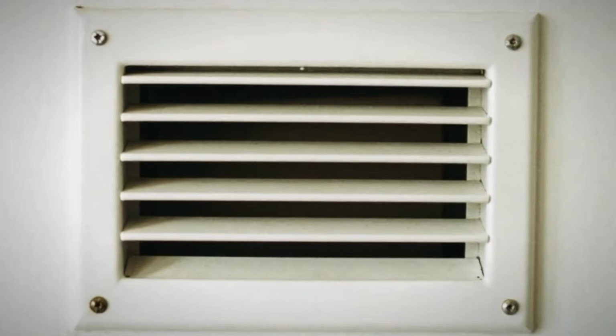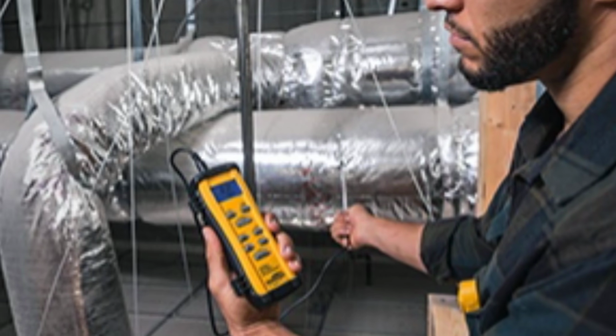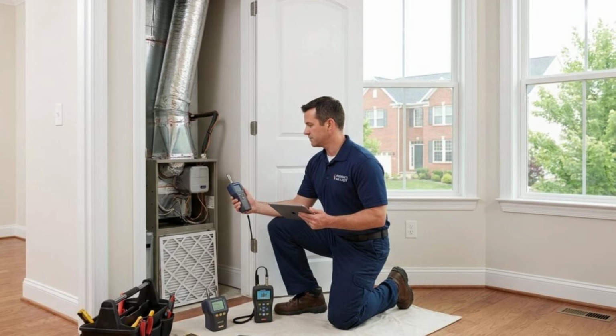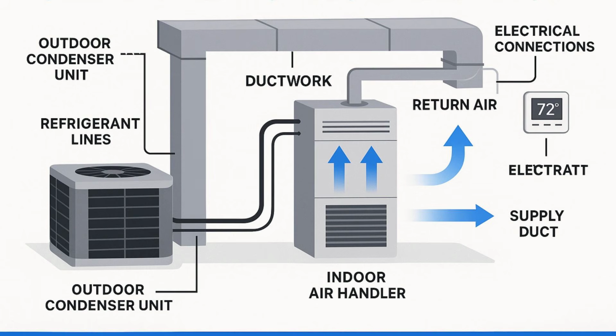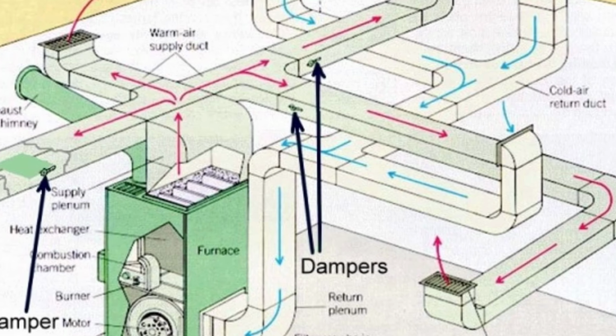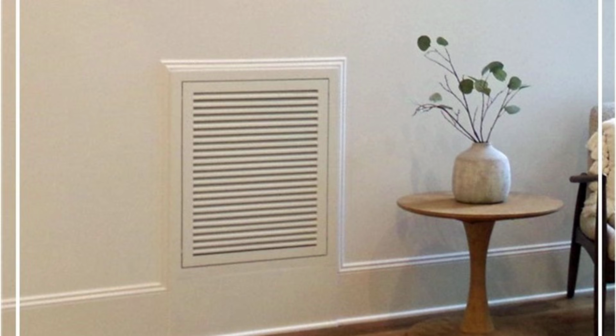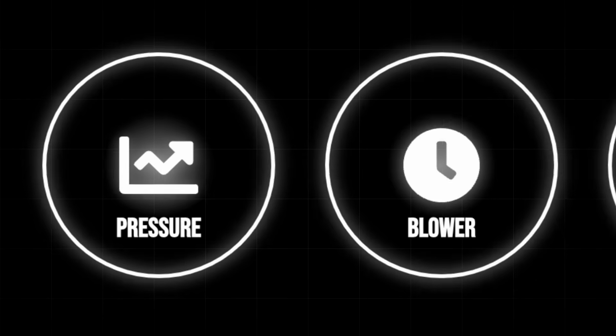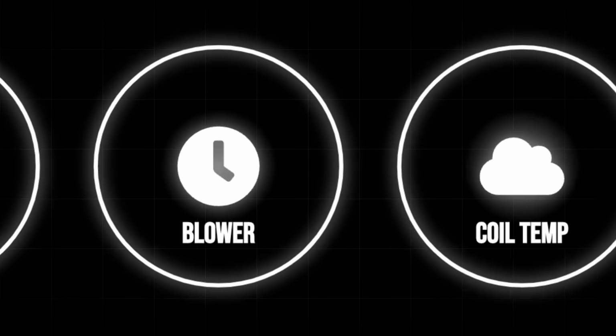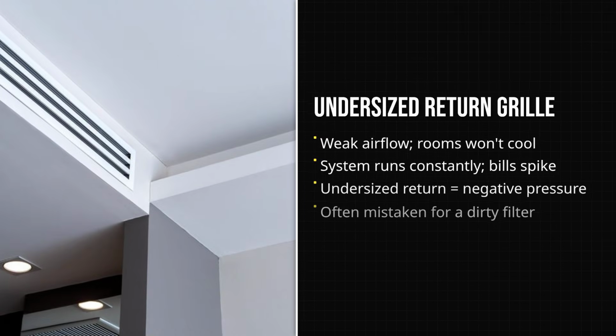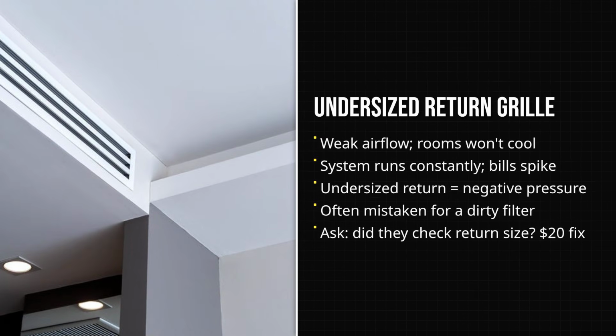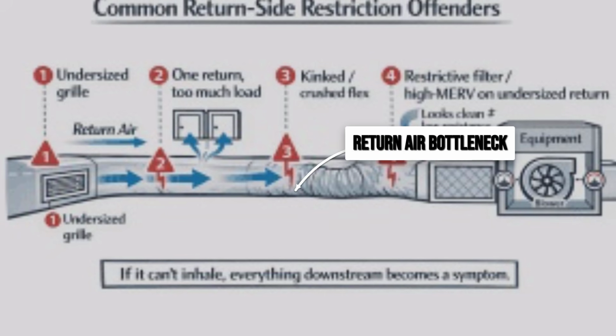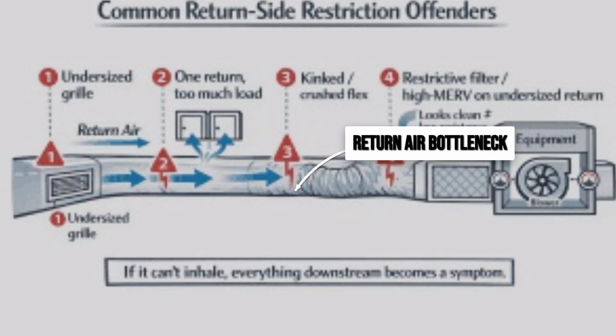I'll be in there. Number 4. Undersized return air. This is one of the most common problems technicians and home inspectors report in older homes. Your cooling system needs to pull air back in at the same volume it pushes out. When the return grill is too small, the system starves. It creates negative pressure inside the ductwork, the blower works harder, and the evaporator coil gets colder than it should. You get weak airflow, rooms that won't cool, and a system that never stops running. Same symptoms as a dirty filter, but no filter change fixes it because the opening itself is the bottleneck.